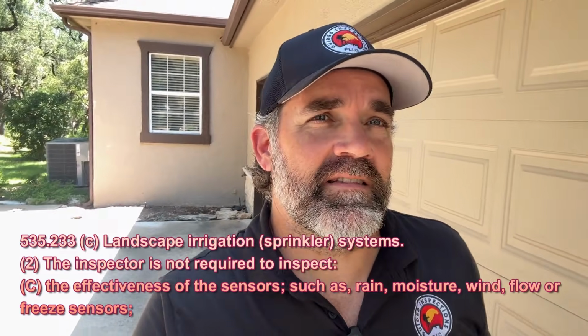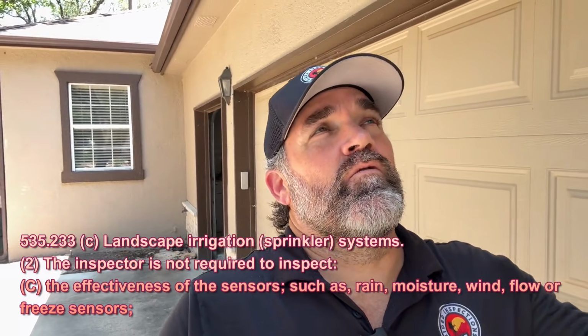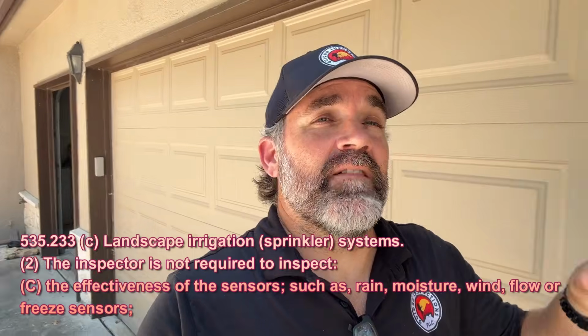Unfortunately, these devices don't always work, and we try our best to determine if they do. Sometimes you can push down on the plunger to manually test it. Our standards of practice actually tell us that we're not required to verify the effectiveness of these devices, but we do need to make sure they're in place and that there's no physical damage to them, to the wiring, to the control panel, and so on.